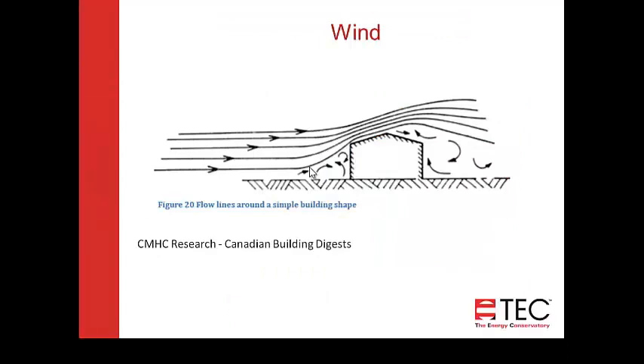Wind effect is another thing that will affect the pressures we see in a building. Wind comes from one direction, blowing over a roof and creating some variable pressures near the building. If we're only measuring one outdoor reference, it's best to do that on the leeward side of the building towards the center of the building, because there's the least amount of fluctuation there. Right up next to the building towards the center on the leeward side is our best location.